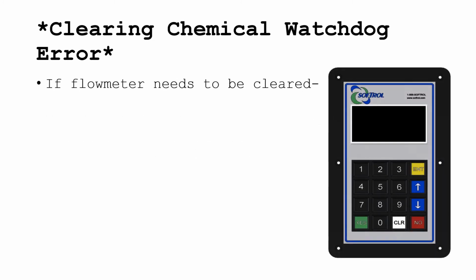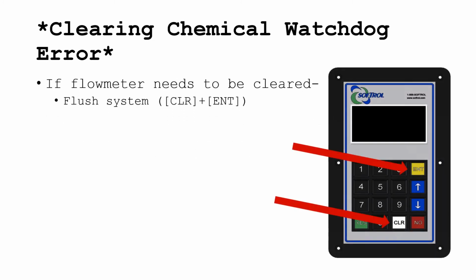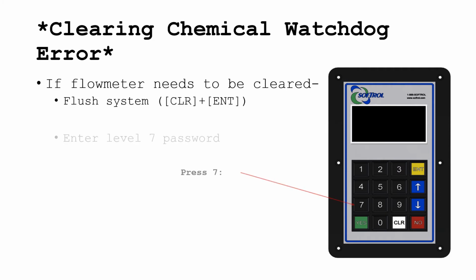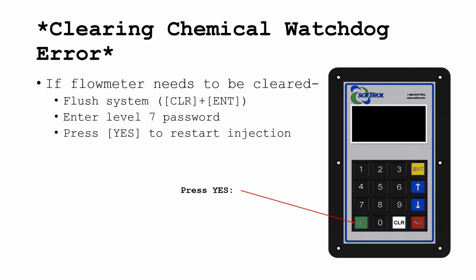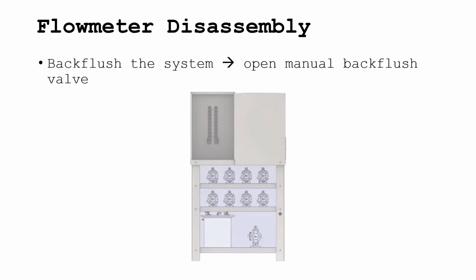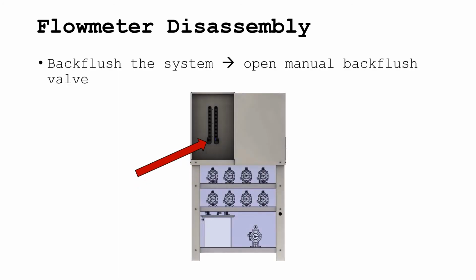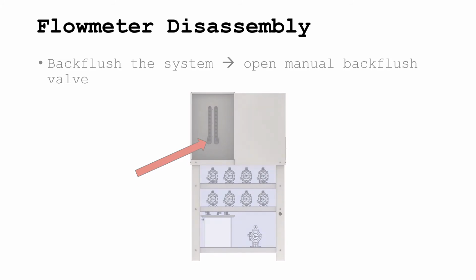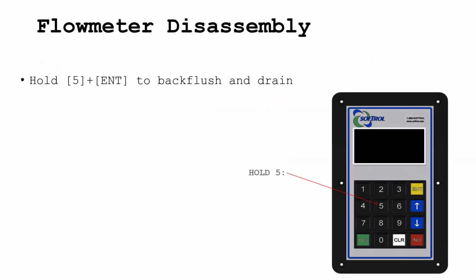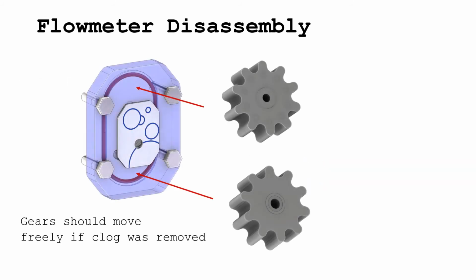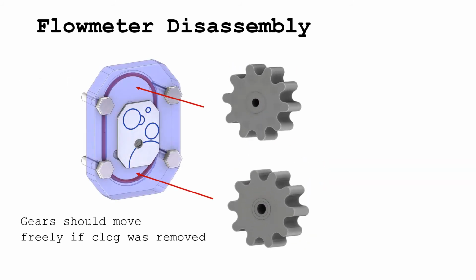If the flow meter needs to be cleared, flush the system for about 15 seconds, enter the level 7 password and press the yes key to restart the injection. If the flow meter is clogged, disassemble the flow meter by doing the following procedure. Backflush the system by opening the manual backflush valve on the back of the manifold. Next, press and hold the 5 and ENT keys to backflush the meter. The gears should spin freely if the clog can be removed.